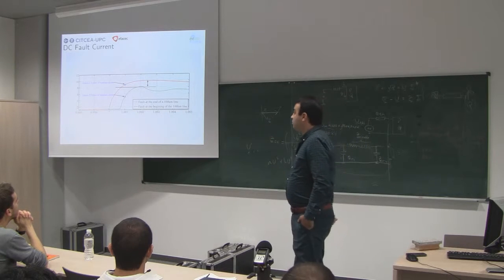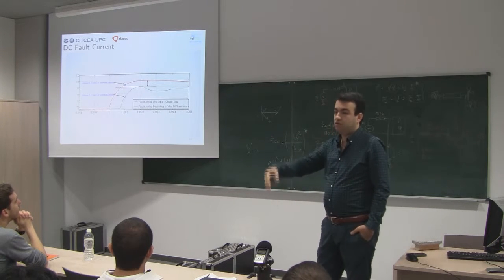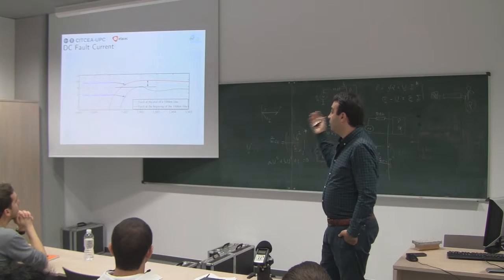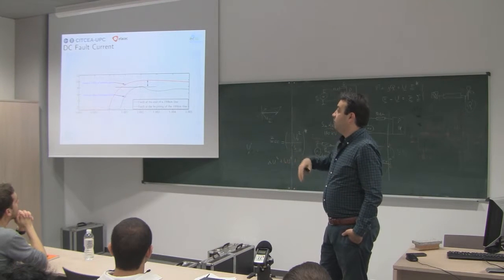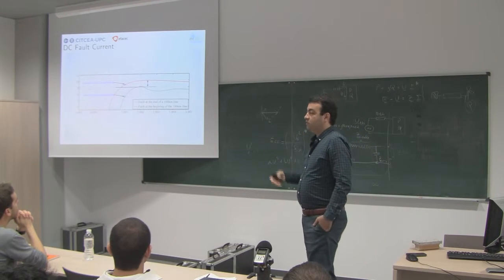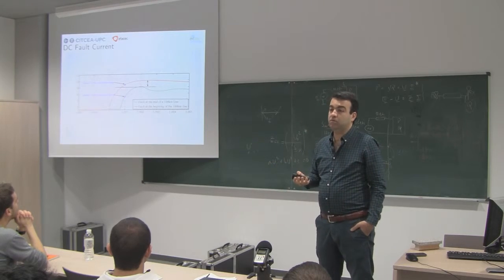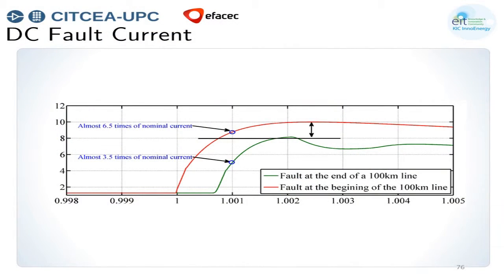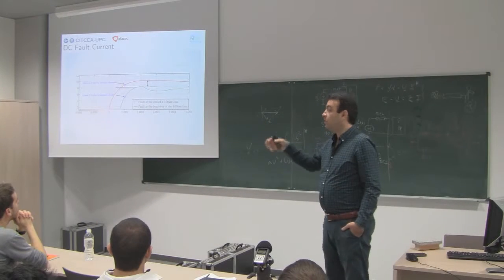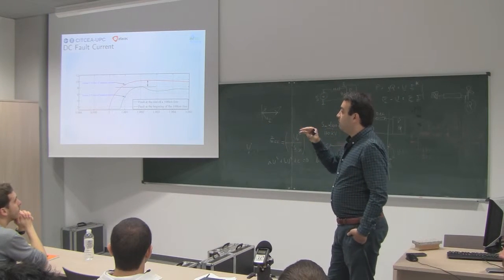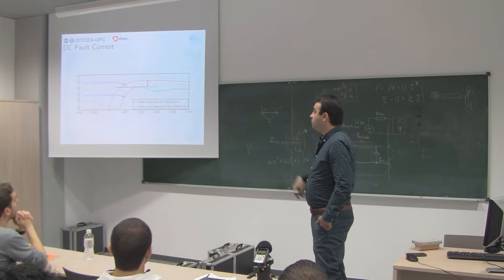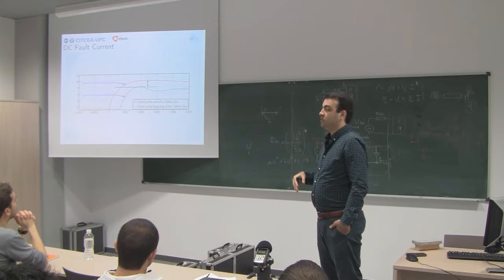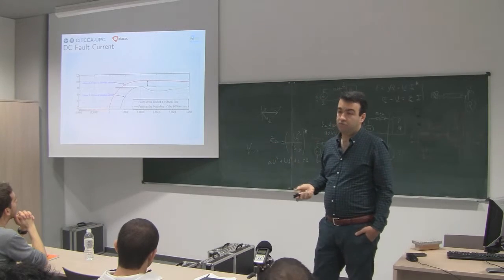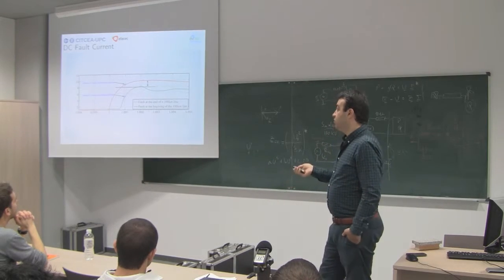If we have the fault very close to the converter, like at the beginning of a 100 kilometer DC line, within 1 millisecond it will reach maybe 6 times its initial, pre-fault current. And if we have it at the end of that line, it will have a delay and a relatively limited peak, but then again within 1 millisecond it will reach 3.5 times its nominal value.